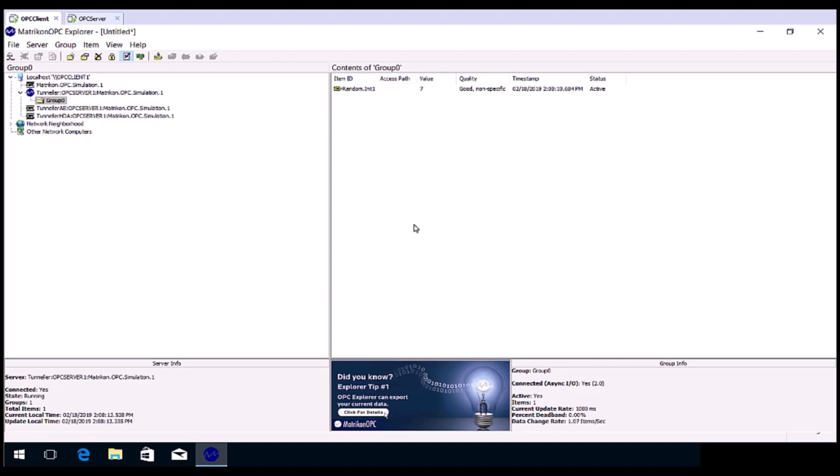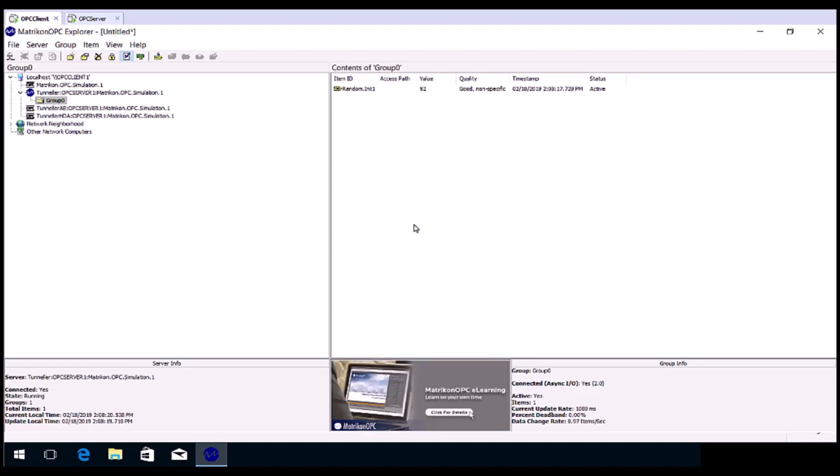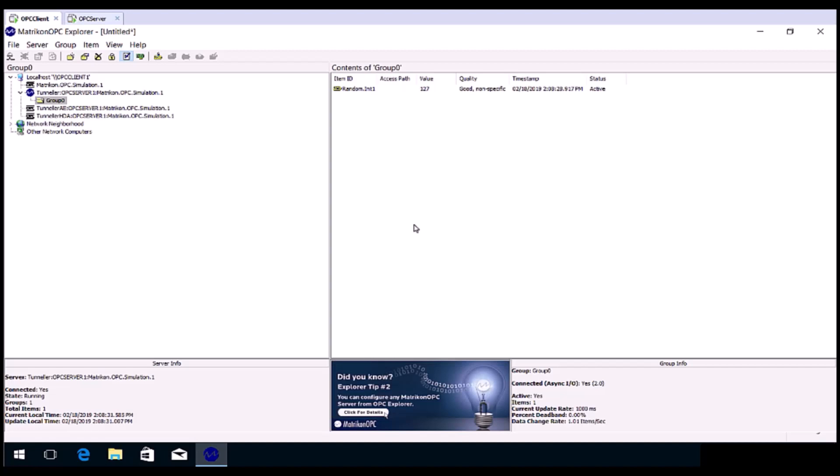If your OPC client requires a host name for the OPC server, be sure to choose local host, or the name of the computer that the software resides on. Remember, Tunneller registers the remote OPC servers as if they are local, so you do not need to specify the details of the remote OPC server, just local host.